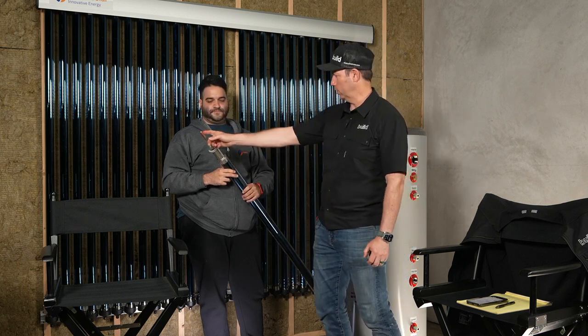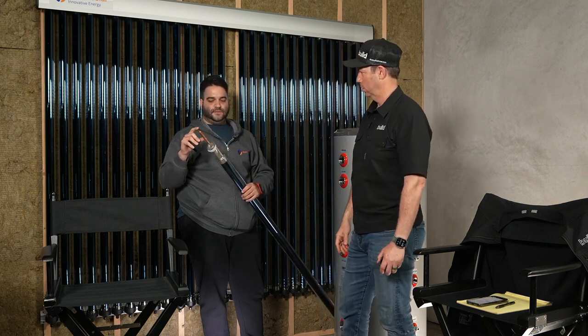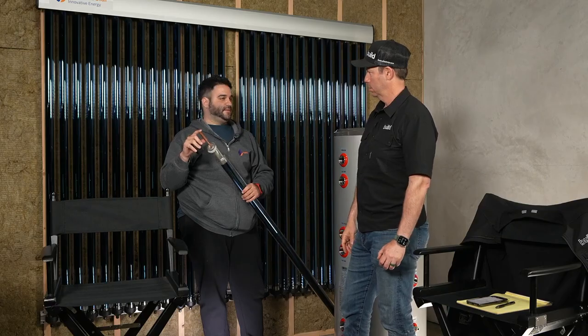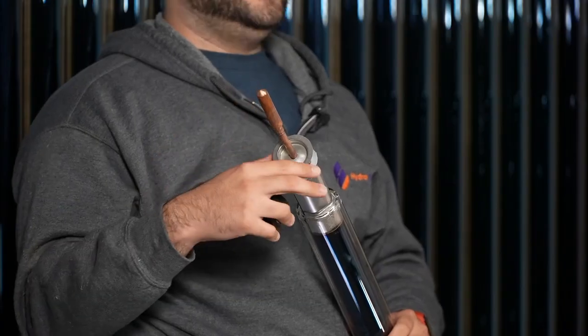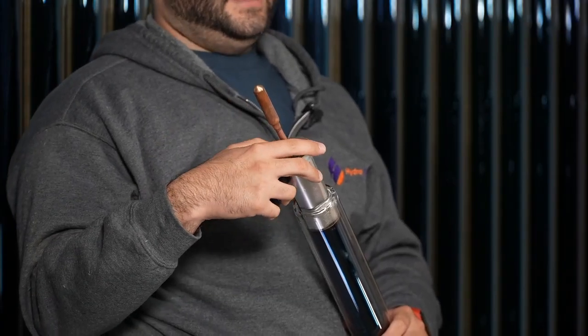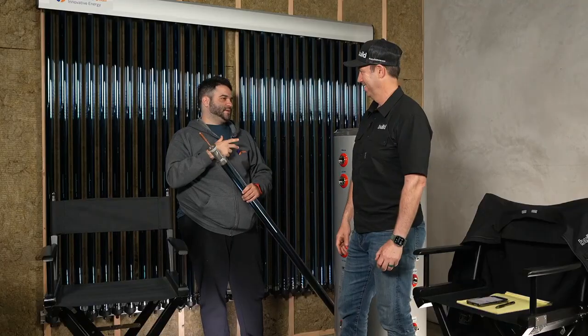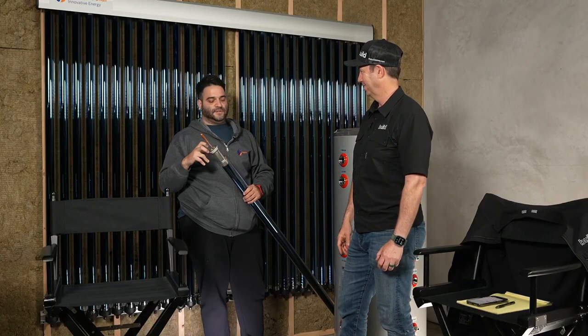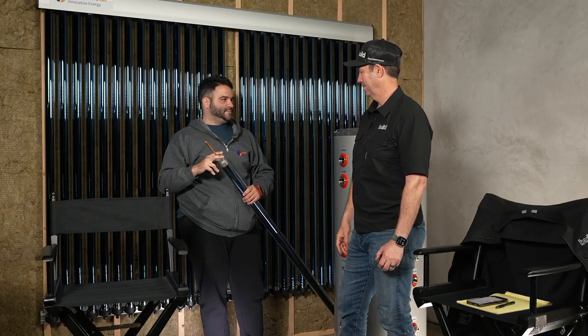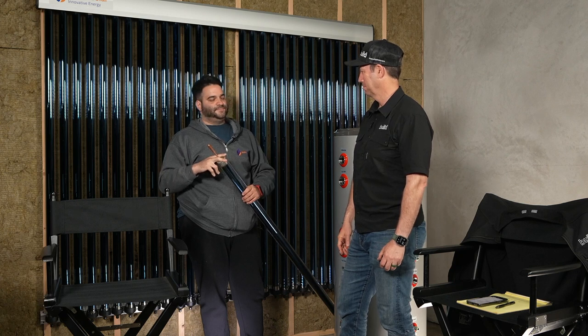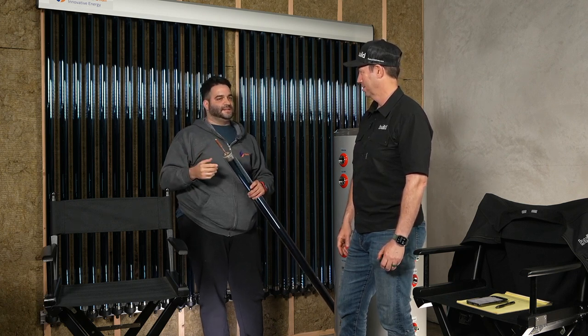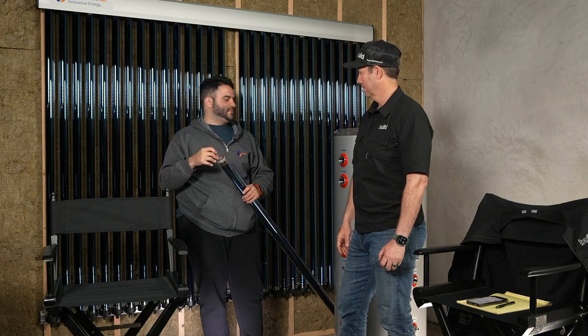Yes. And how hot is this getting up here at that gutter? The bulb can actually go up to like 500 Fahrenheit theoretically. Holy cow, that's hot. Theoretical maximum on the gutter system itself, or the manifold as you call it, we're looking at 300 Fahrenheit maximum. Typically, since you want to keep costs down on pumps and fittings and O-rings and whatnot, you're probably going to want to run below 200 Fahrenheit, so below boiling point.